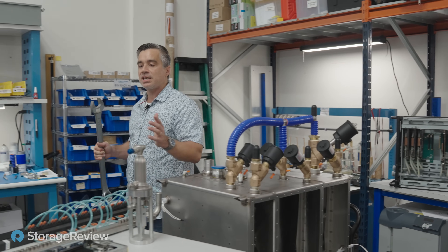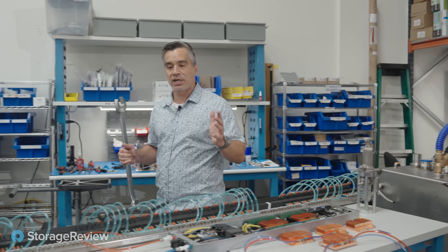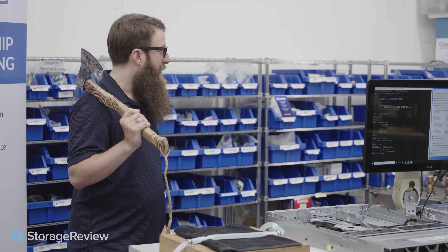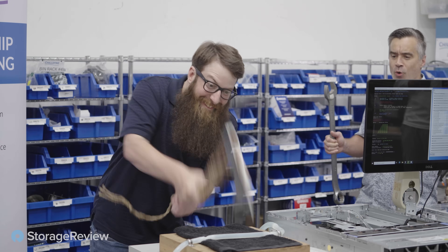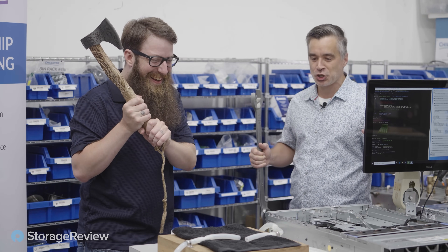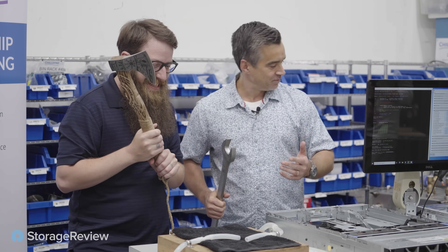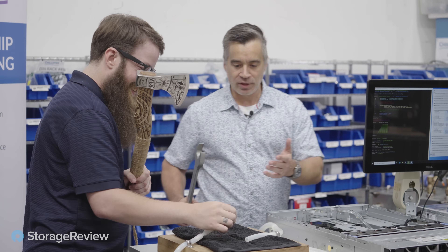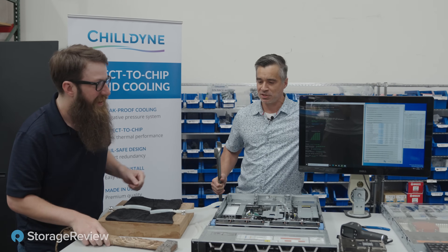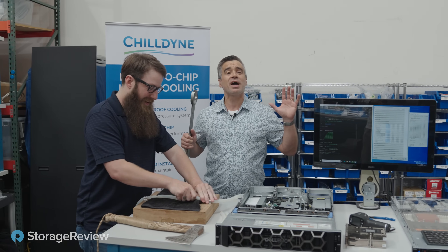While it's mostly data center, all of this technology and knowledge is really cool and really special. And Jordan — what are you doing over here? You said any leak. He just tomahawk chopped the line! Yeah, it didn't leak. So not only is it not leaking, these two systems are still running and the CDU is happy as can be. It doesn't care.